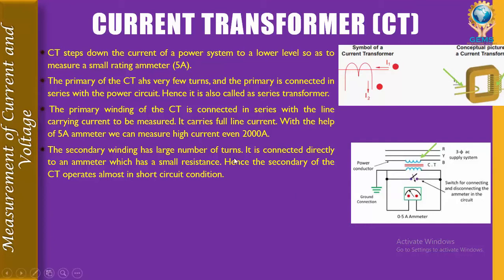So this is a very important precaution that we have to take when we operate this current transformer. The current transformer should always be operated in short circuit condition, especially while disconnecting the ammeter. It should always be operated in short circuit or closed mode. You cannot open it because it is a series transformer.